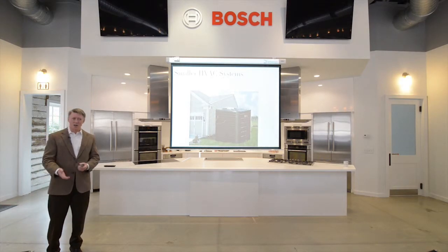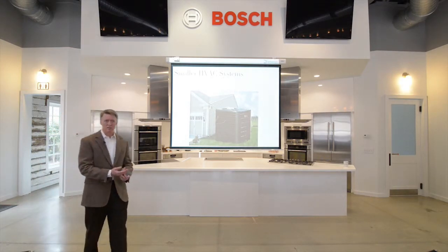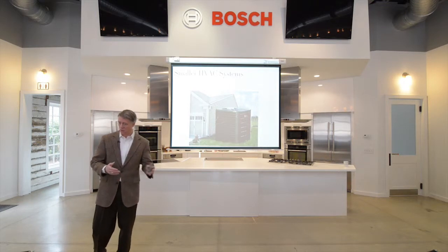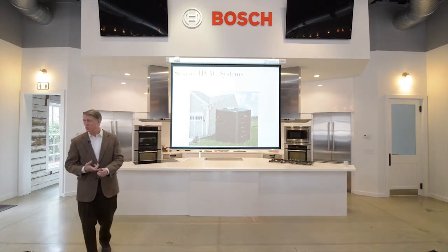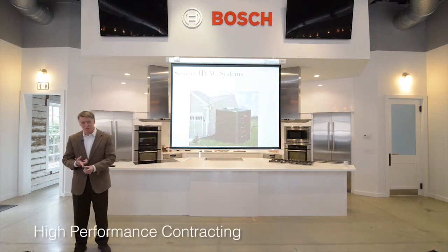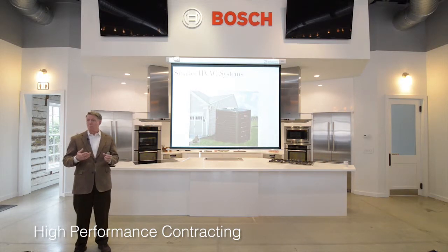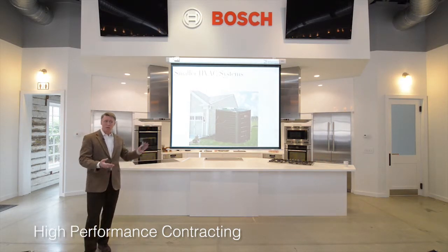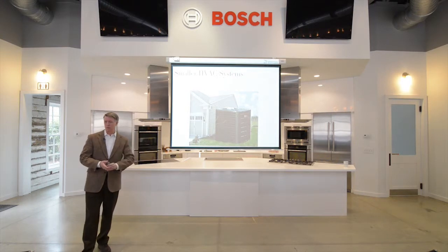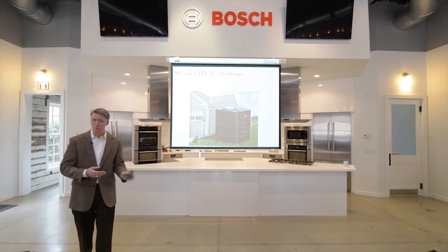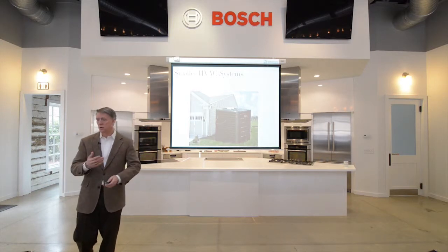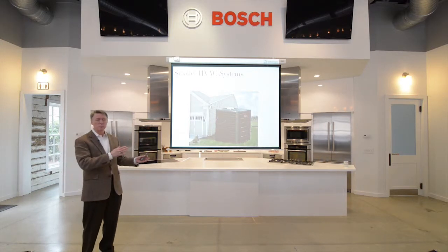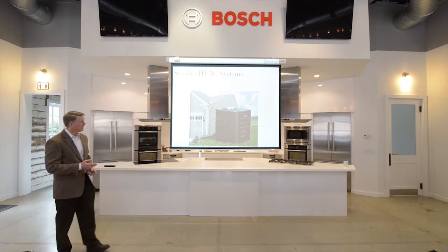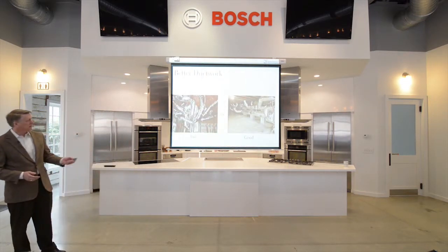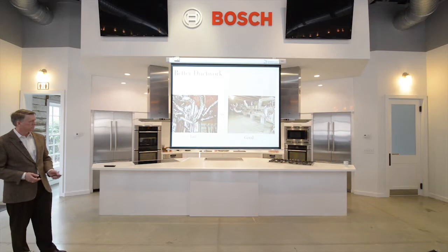And in a green home, it's supposed to be done right, and there are third-party inspections that help make sure that it's done right, and they measure the leakage in the duct system. They measure airflow. In the Energy Star version 3 now, the HVAC contractors and the raters have to measure the airflow, make sure that the system is commissioned properly so that it's moving the correct amount of air to every room. So that's one thing. Here I'm talking about ductwork.